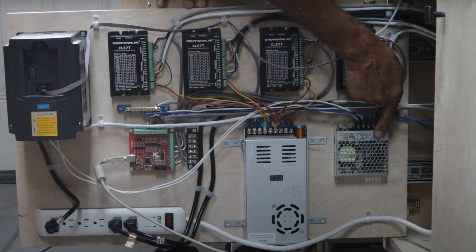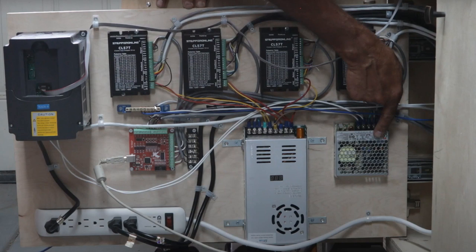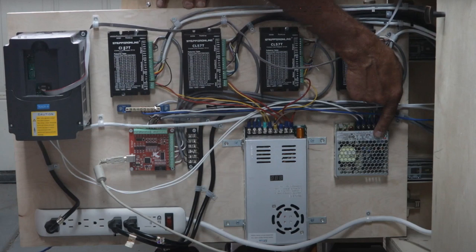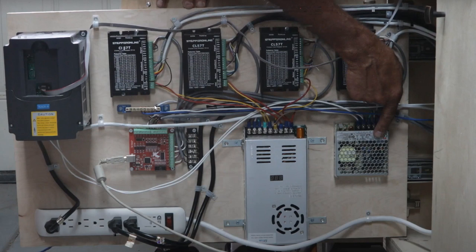You see multiple terminals now being jumpered - that is incorrect. That is because the individual once again does not understand the terminal splitting, which simply means we use a terminal similar to what we see here and you have one lead come over to this terminal, basically adding additional terminal spaces. This is how you can easily see if someone understands electronics or they do not. And why I say that is essentially what they end up doing is making a convoluted mess when it doesn't have to be. It would be much more organized to have a single lead come over to this terminal and by doing so they've split the terminal and then all they do is run individual leads coming to this and it keeps everything extremely neat. Now saying that is something that is easy to do, doing it takes more time and henceforth more time, more money because he needs more terminals.